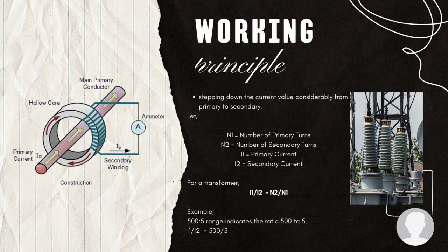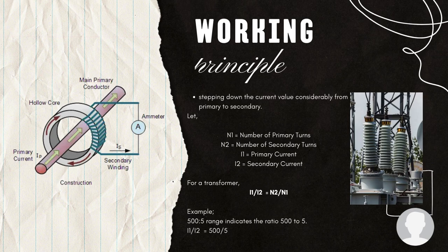Let N1 be the number of primary turns and N2 be the number of secondary turns. Let I1 be the primary current and I2 the secondary current. For a transformer, I1 over I2 equals N2 over N1. As N2 is very high compared to N1, the ratio I1 to I2 is also very high for a current transformer. The current ratio indicates the range of the current transformer. For example, a 500:5 rating indicates the CT steps down the current from primary to secondary by a ratio of 500 to 5.